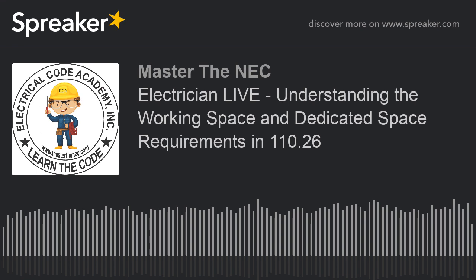Okay, if I'm dealing with an existing dwelling unit, and this is very common where we have dwelling units that might even have something down in a dry crawl space or something that might not be qualified as a basement, but it's like a basement, and they have a panel down there, they put it there, it is what it is, it's existing, and they don't meet the height requirement. Okay, there is no break on the width and depth, although it probably didn't care about that in the past either, but in an existing application, when I'm dealing with that, then the height can be reduced to less than 6.5 feet.